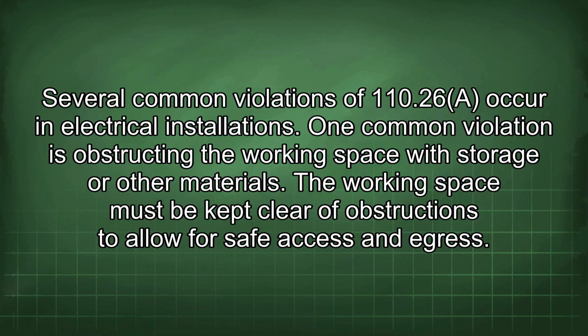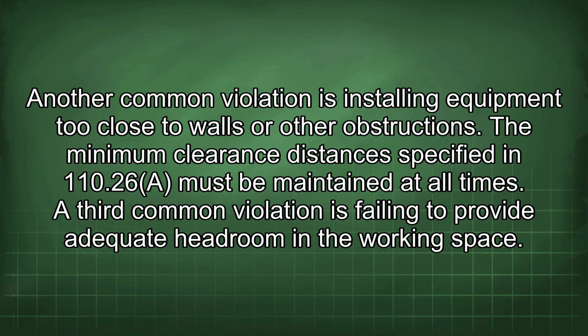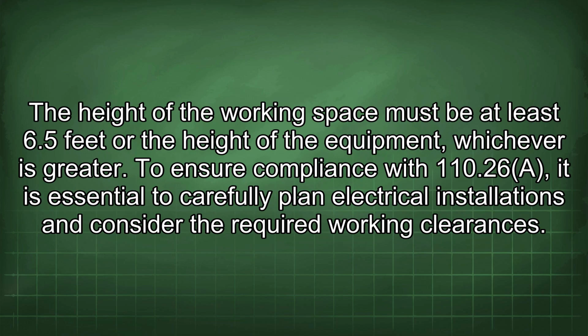Several common violations of 110.26 occur in electrical installations. One common violation is obstructing the working space with storage or other materials. The working space must be kept clear of obstructions to allow for safe access and egress. Another common violation is installing equipment too close to walls or other obstructions. The minimum clearance distances specified in 110.26 must be maintained at all times. A third common violation is failing to provide adequate headroom in the working space. The height of the working space must be at least 6.5 feet or the height of the equipment, whichever is greater.